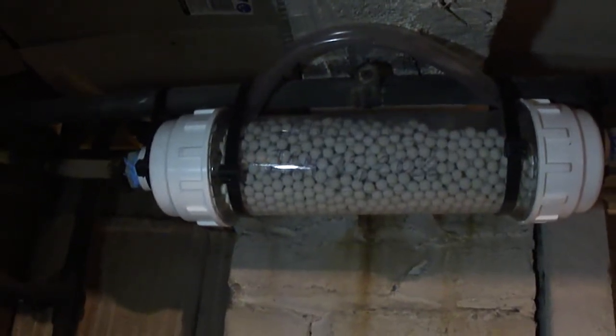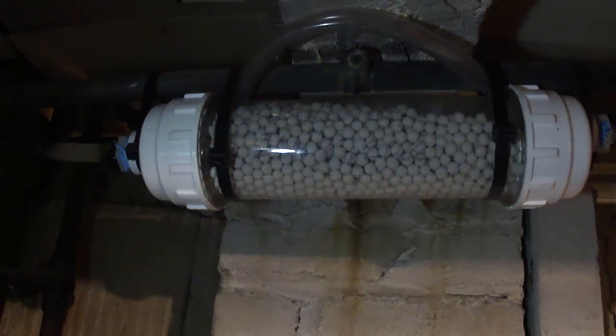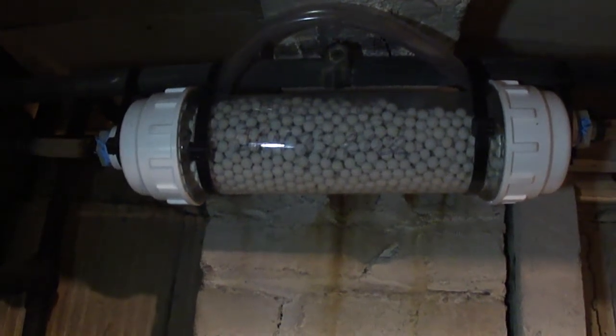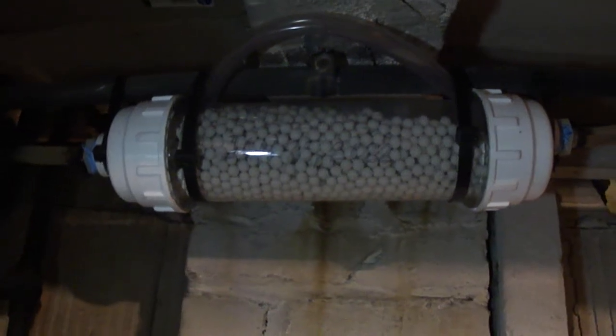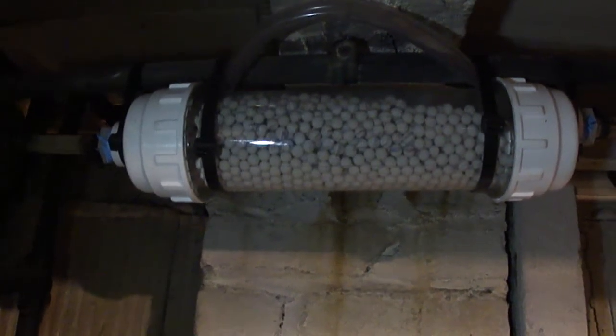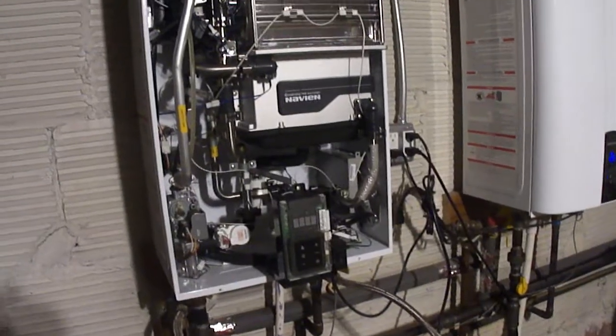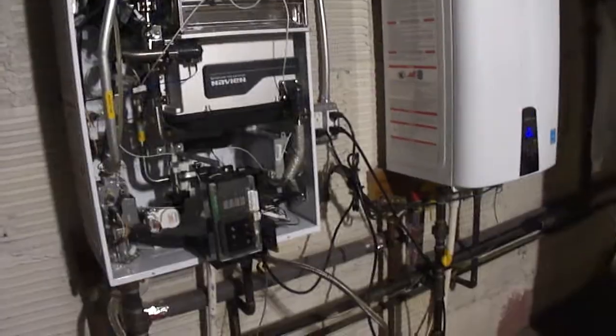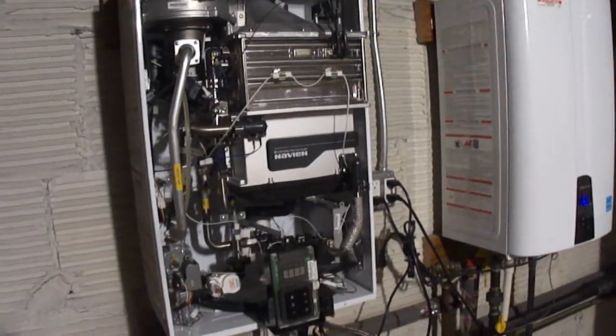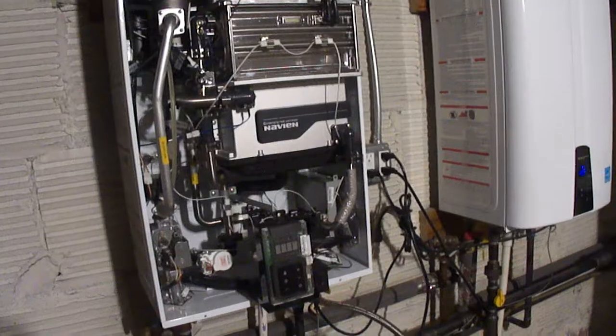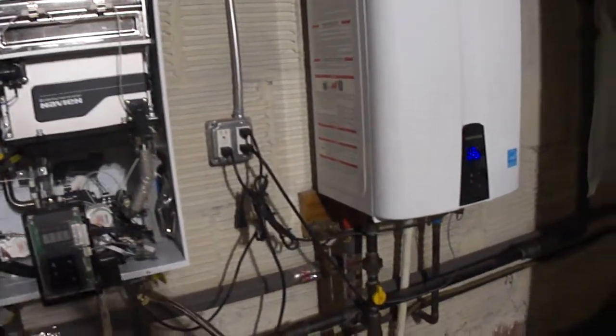And here you're looking at the condensation neutralizer. What this thing does is it neutralizes the acid from the condensation before it goes into the sewer system. So whenever it needs changing, just change it. This is a dual machine, and when you shut off one, they're connected in cascade mode. So one is the master and the other one is the slave unit. We're working on the slave first. On the master unit, you might get an error like this one over here, E736. That indicates there's a communication error, so ignore that.